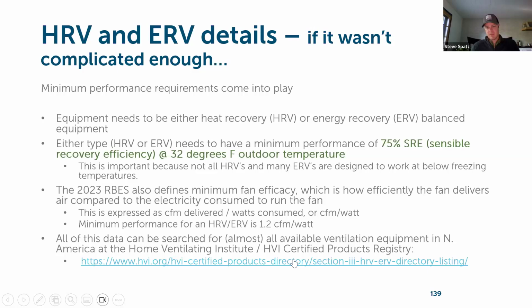So I'm going to show you some information here in a few minutes about how to find equipment that is actually specifically rated and tested at low outdoor ambient temperatures, because that is the critical time when we really need these systems to be performing, in those cold months of the year. So there's definitely a distinction in equipment available in the market between what's cold climate rated and tested versus equipment that is not.